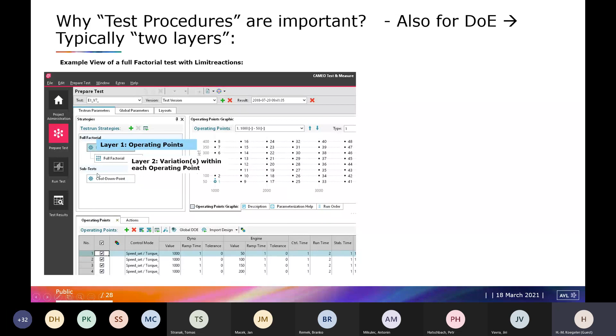And now let's have a look what is happening during test run. So this would be maybe the first layer, and we have done the points up to here. And if it comes to that point, in each of the layers the same happens. First, an operating condition is set, then stabilized, and if you want, you can make a first measurement there. Typically in between, you have trigger points, which are named intuitively: before stabilization, after start, before measurement, after measurements. And at that point here, which is marked, it automatically goes to the second layer. And here it does again the same.